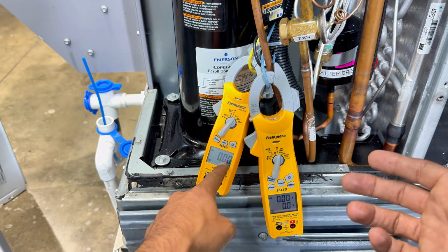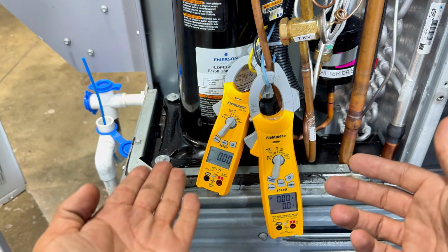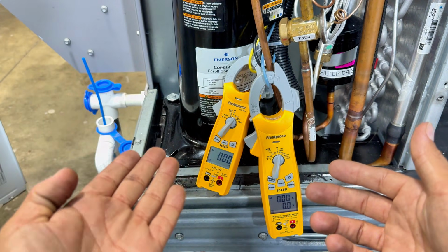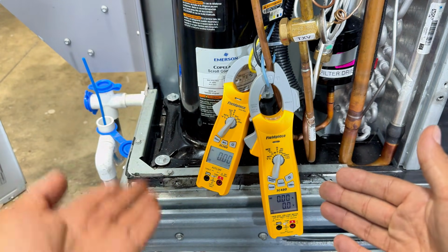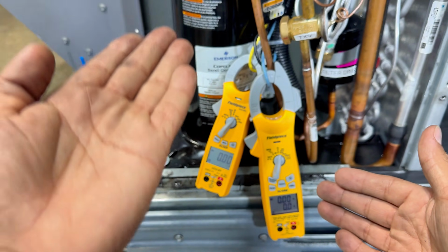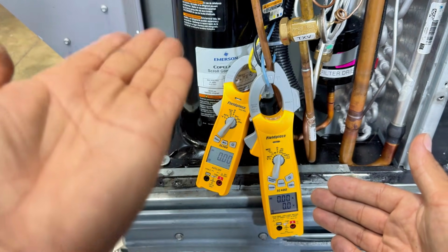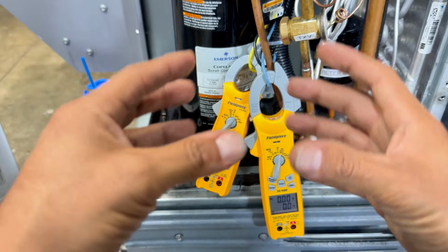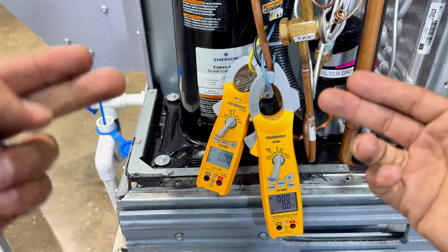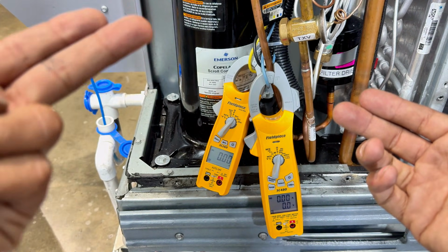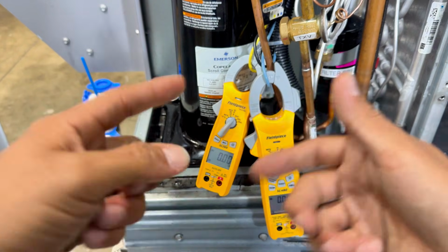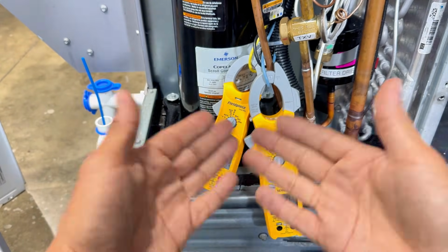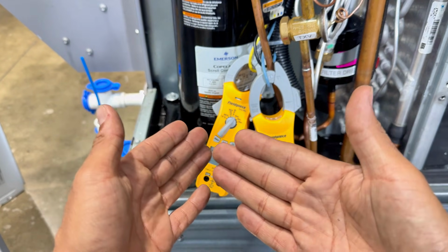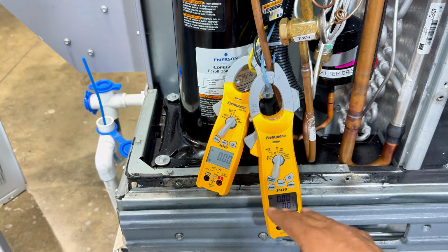But when the capacitor is good, it is normal for that run winding current to go up, but then it comes down pretty fast. But how high it goes up matters. When it goes up really high, it tells you to ask why it had to go up that high to get the compressor to turn on. Because typically when it was on with the good cap, as you saw in the previous clip, that was about 4 amps.